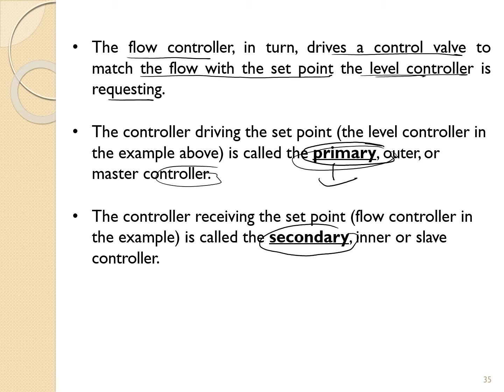The controller driving the set point, the level controller in the example above, is called the primary or outer or master controller. The input of the set point is fed into our primary controller, which is the level control just now. The controller receiving the set point is our secondary controller. So the output from the primary is sent to the secondary controller, which receives it as its set point. This secondary controller is also called the inner or slave controller.